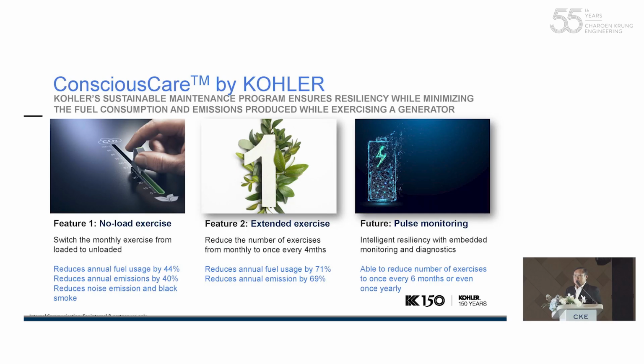It's recommended to exercise your genset monthly, 12 times a year. With the conscious care program, you can reduce it to once every 4 months—just 3 times a year. This reduces fuel consumption by up to 71%, even better than the no-load exercise, and annual emissions by 69%. This is what we're offering right now.